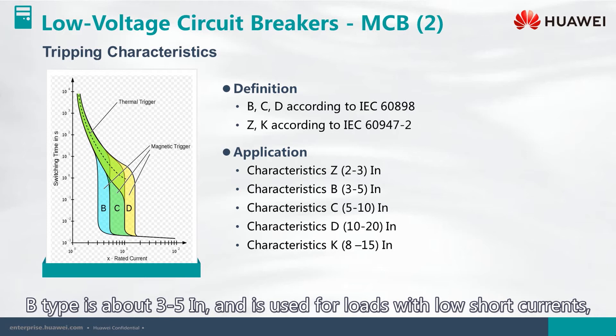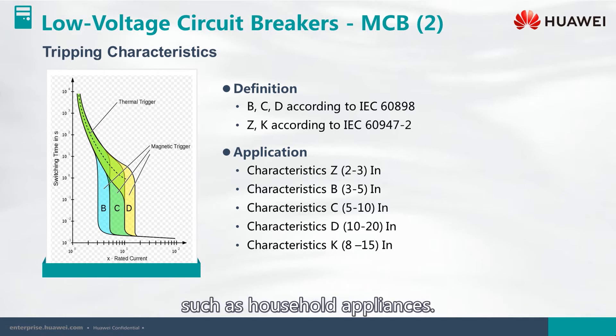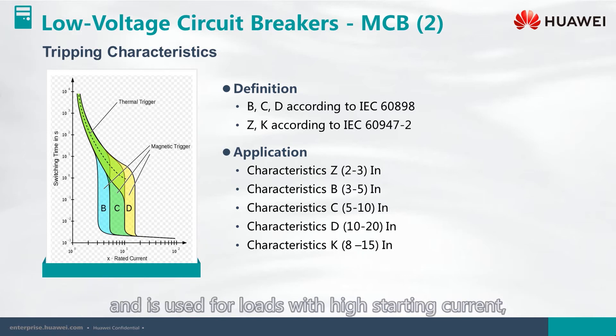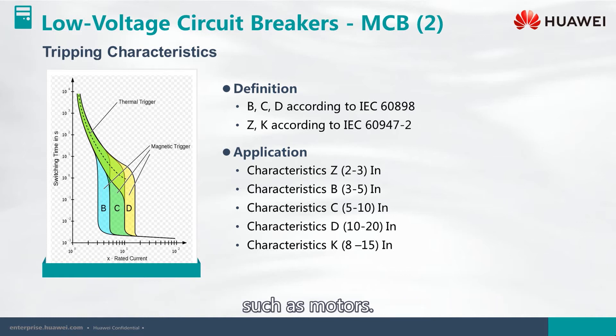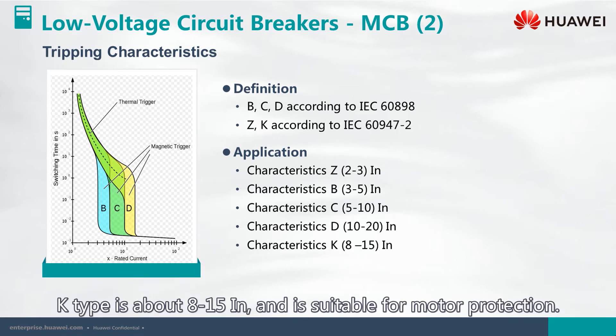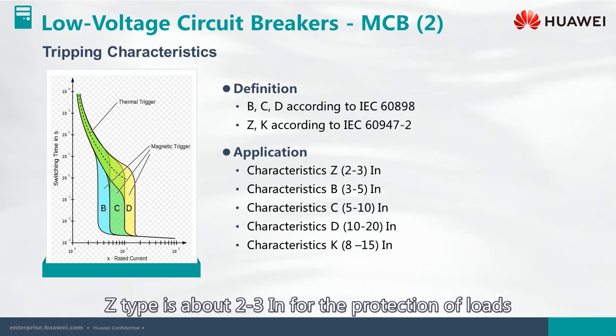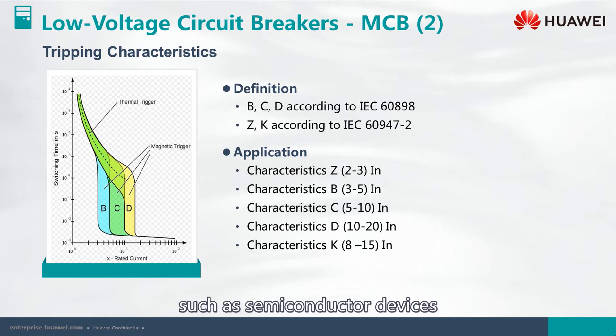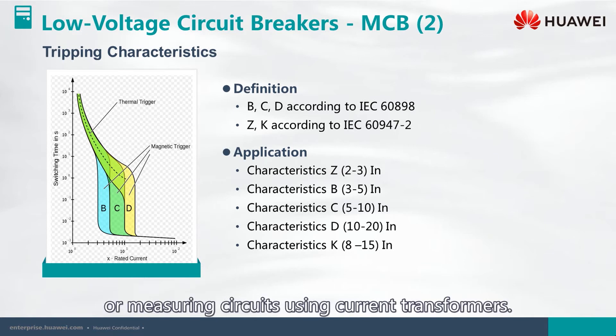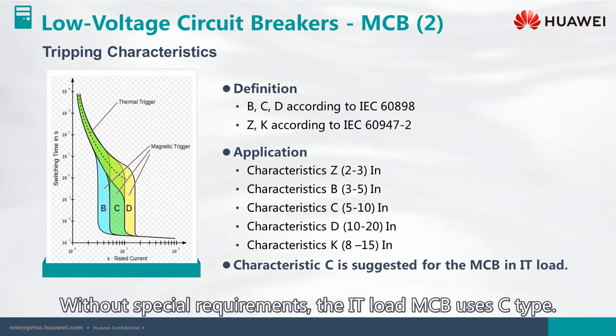B type is about 3 to 5 times rated current, used for loads with low short-circuit currents such as household appliances. D type is about 10 to 20 times rated current, used for loads with high starting current such as motors. K type is about 8 to 15 times rated current and is suitable for motor protection, with thermal tripping starting at 1.2 times rated current. Z type is about 2 to 3 times rated current, for protection of loads such as semiconductor devices or measuring circuits using current transformers. Without special requirements, for IT loads, MCB uses C type.